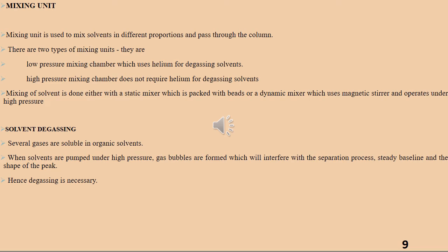Solvent degassing. What is solvent degassing? Several gases are soluble in organic solvents. When solvents are pumped under high pressure, gas bubbles are formed which will interfere with the separation process, steady baseline and the shape of the peak. Hence, degassing is necessary to avoid these problems.